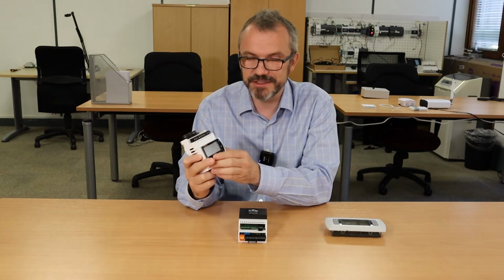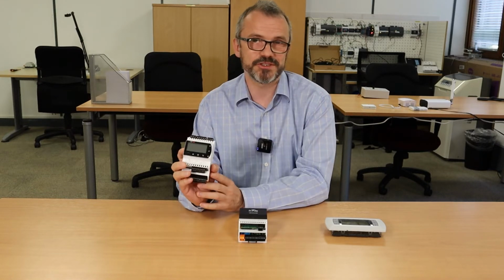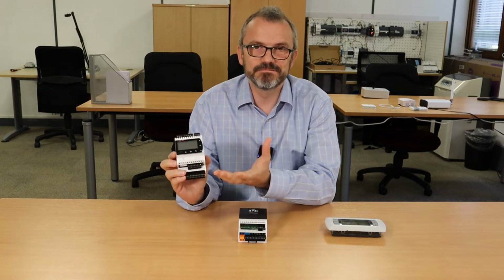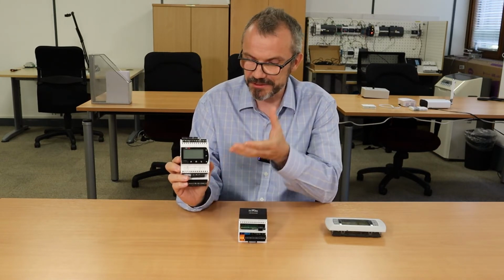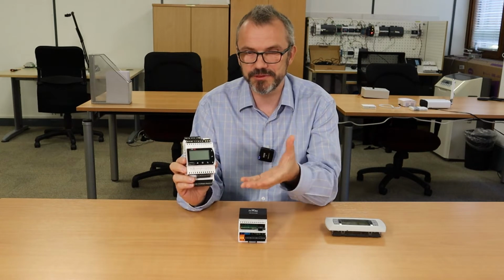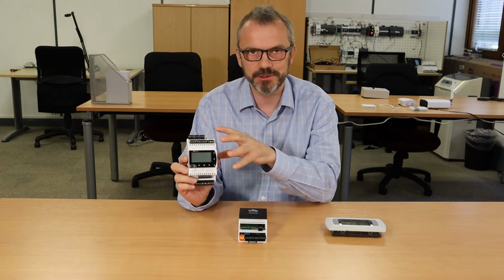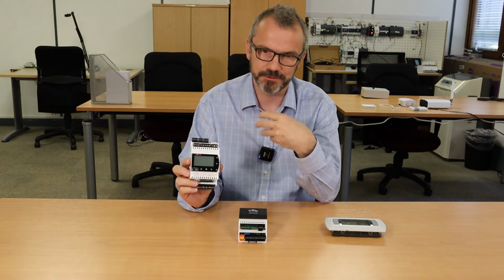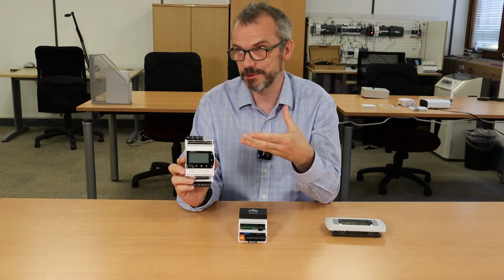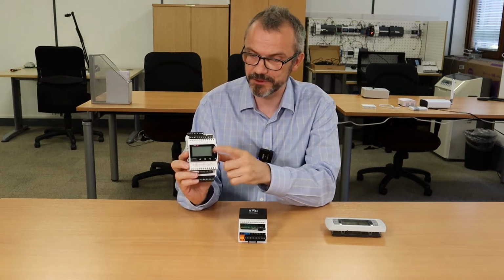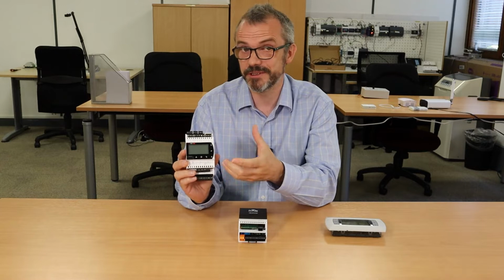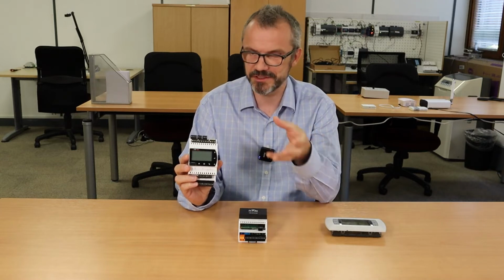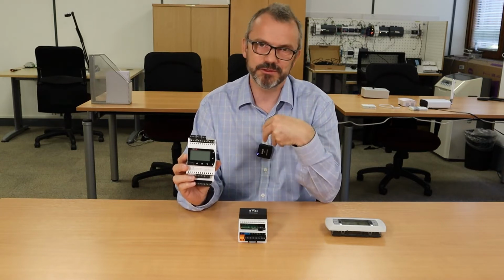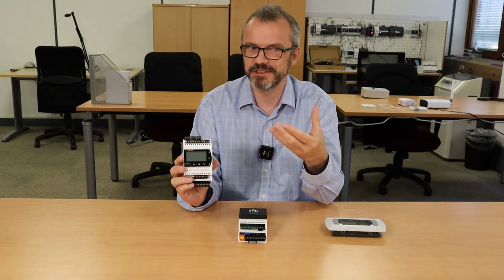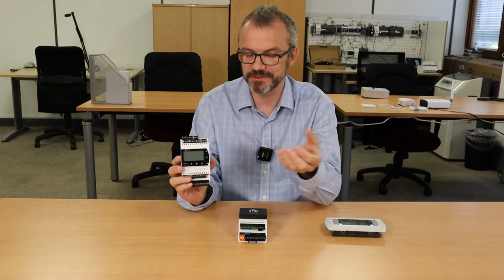So the last thing to say is that it's got a built-in watchdog. As we said before in other videos, that's a great thing to have in a critical environment where if you were to lose the BMS for whatever reason, a comms problem or any hardware, firmware or software failure, basically you can configure the outputs on this as required to maybe run a couple of chillers and a set of pumps to keep your critical chilled water system running, say in your data center. So that's a very useful feature.